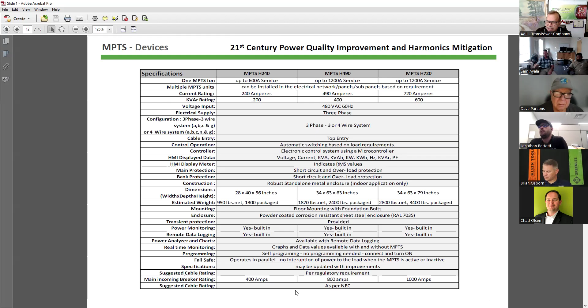This is a specification sheet for all the units I just showed you in the previous slide. There's one more model called MPTS 120, and that is now under special manufacture. It's not produced during normal production batches, because we noticed that most panels and loads, the minimum panel is 200 or 225 amps. It could be 400 amps, it could be 600 amps, but very rarely do you have a 100 amp panel. And even if you have a 100 amp panel, the load is only 30 amps, because that panel is overdesigned and oversized to deal with electronic and voltage variations to avoid tripping.